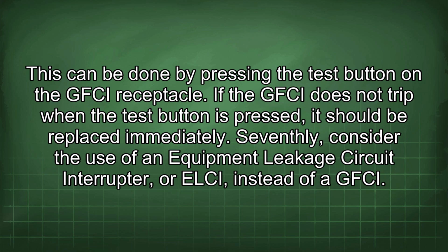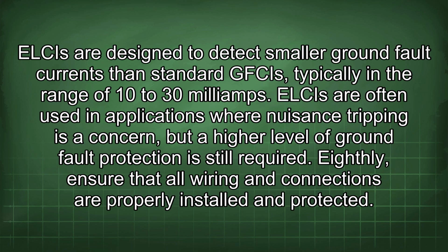Seventhly, consider the use of an equipment leakage circuit interrupter, or ELCI, instead of a GFCI. ELCIs are designed to detect smaller ground fault currents than standard GFCIs, typically in the range of 10 to 30 milliamps. ELCIs are often used in applications where nuisance tripping is a concern, but a high level of ground fault protection is still required. Eighthly, ensure that all wiring and connections are properly installed and protected.